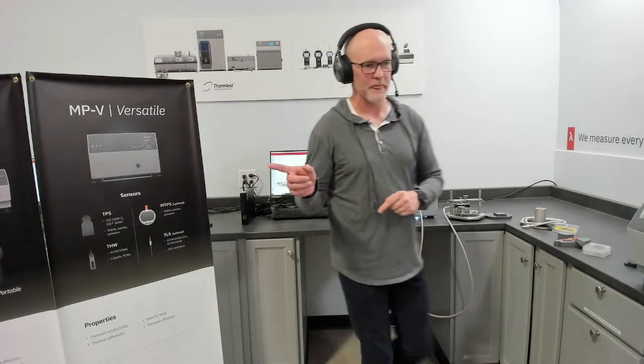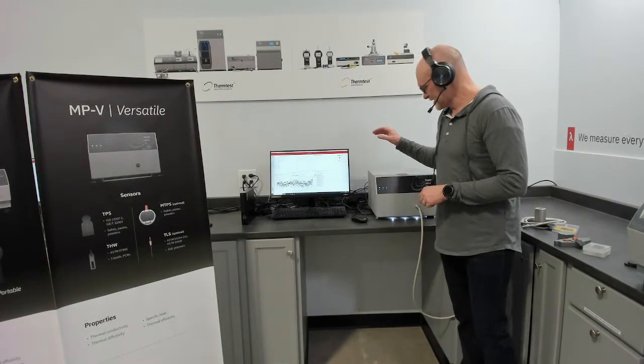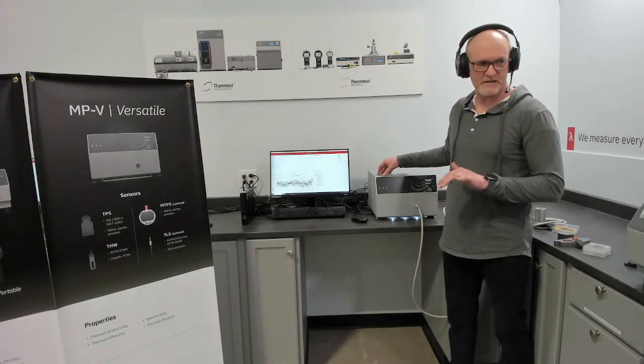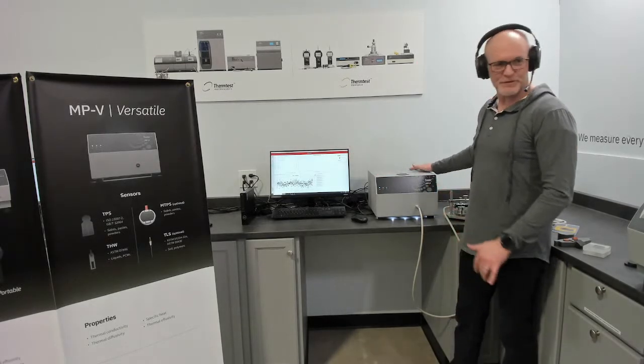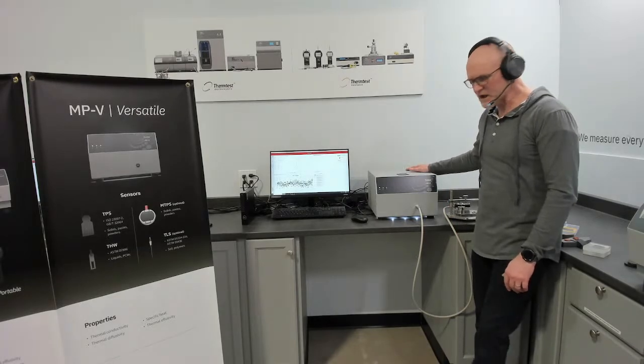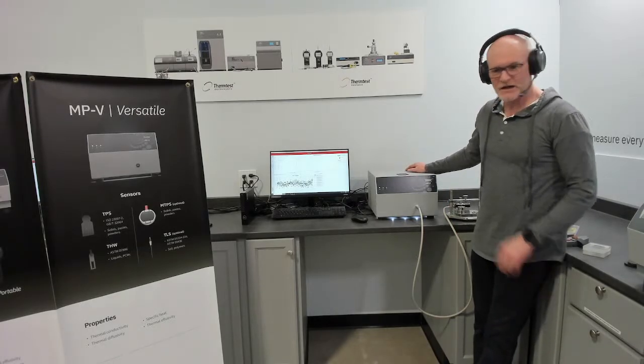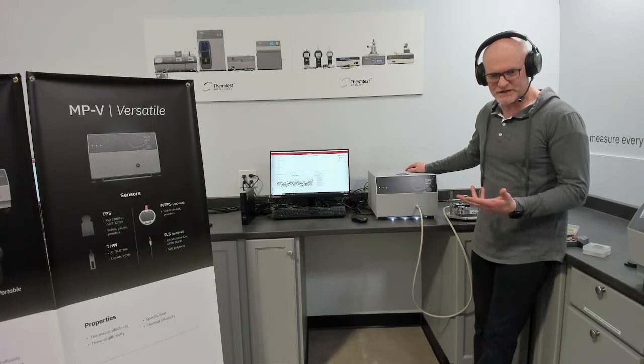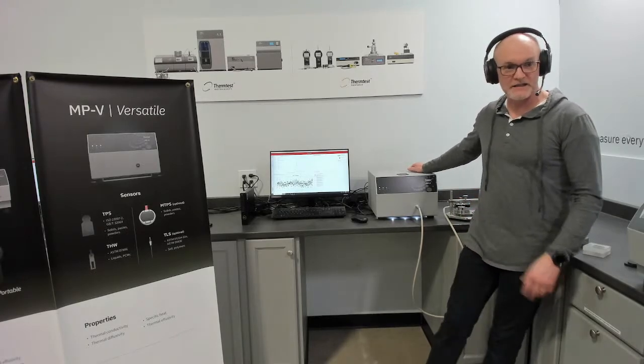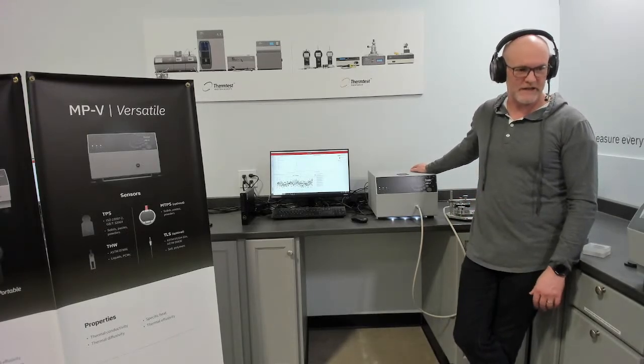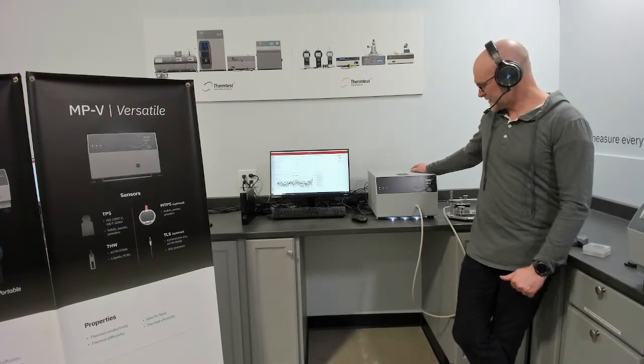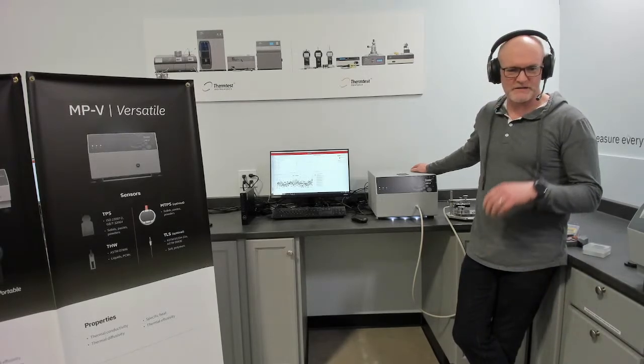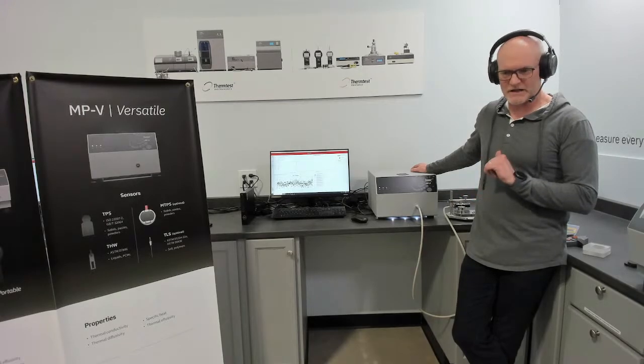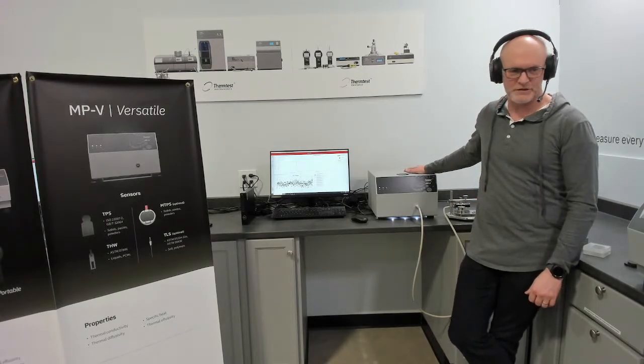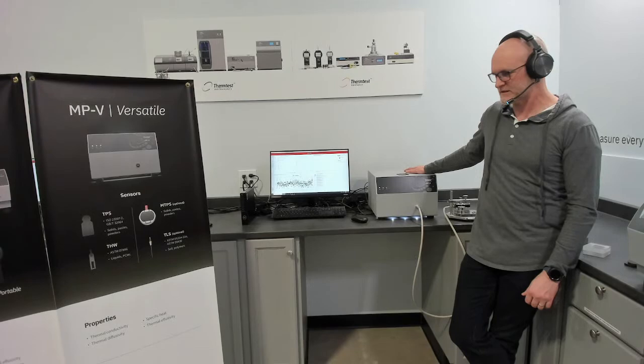But before we go, I'll get out of the way and talk a little bit about the controller, test time, and the software. The MPV controller itself has variable test time, again following the ideal theory of transient plane source. It leads the industry in detection of data points per second, as well as a Wheatstone bridge following the ISO. So it's really important that we've constructed a unit to follow the standards as they're written.